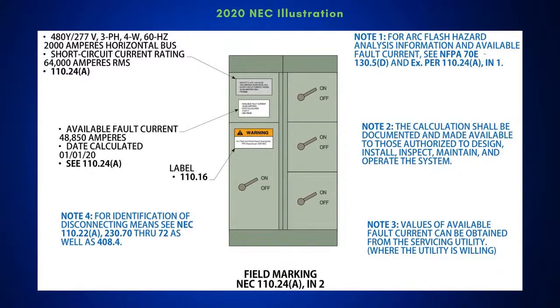So when you look at this, here we get into the field marking, and you see all the information that's required here. You've got your available fault current; we're telling you here that it was 48,850 amps, and we just said the date it was calculated was 01/01/20. And we're telling you what type of equipment it is and everything. We put a whole illustration here to give you an example, and then all the notes that you need to consider here.